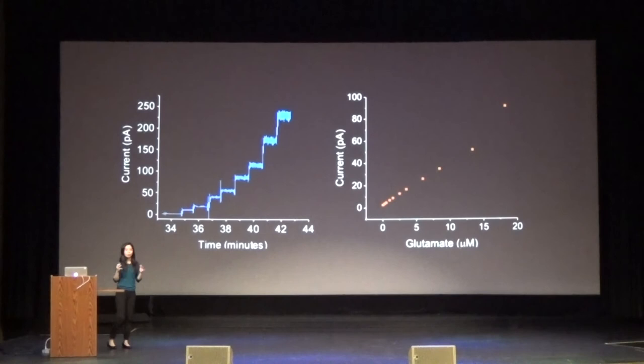By the end of the calibration curve, I can calculate a slope on this right-hand side, and I use that number to compare how the slope changes the longer the device soaks in each of these soak solutions.